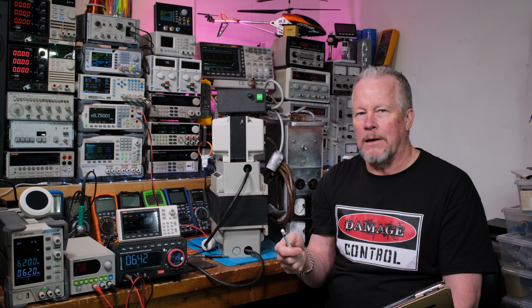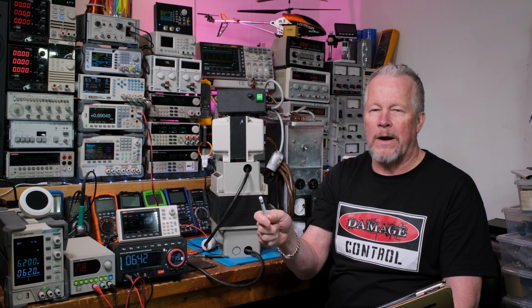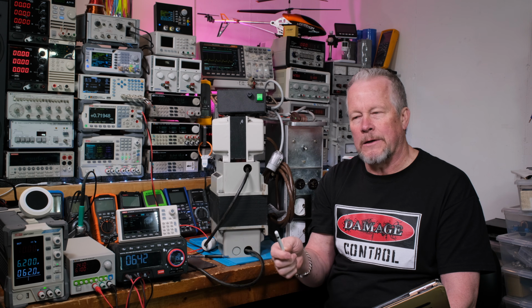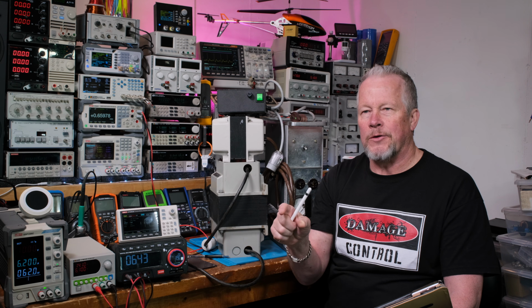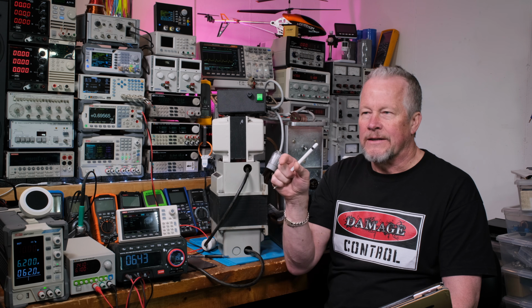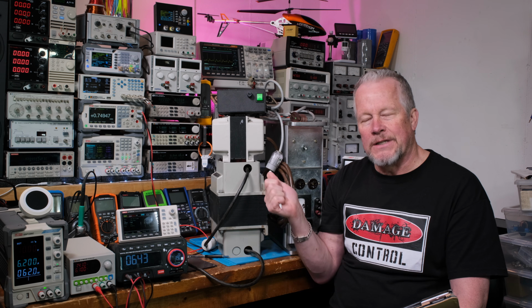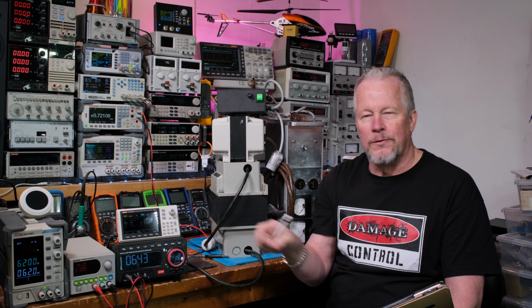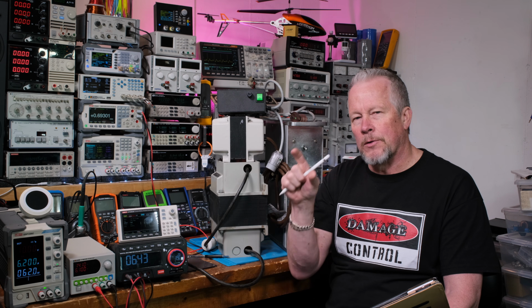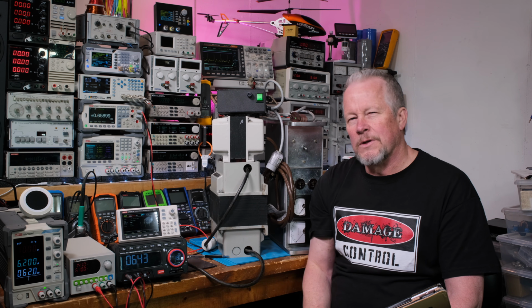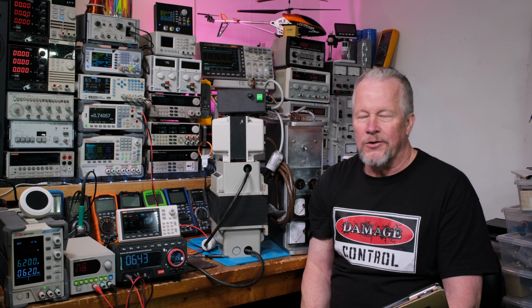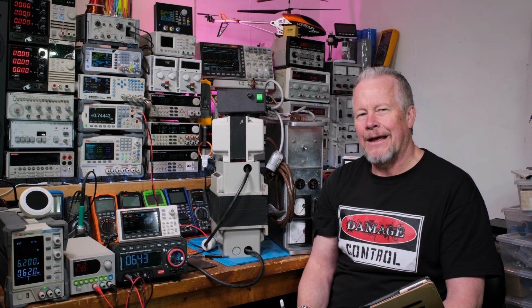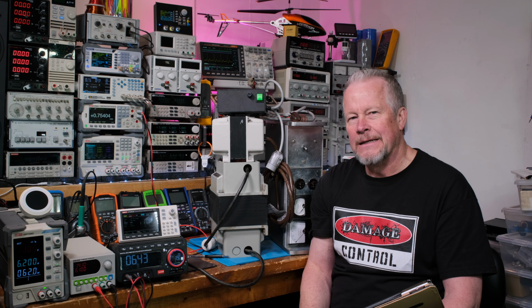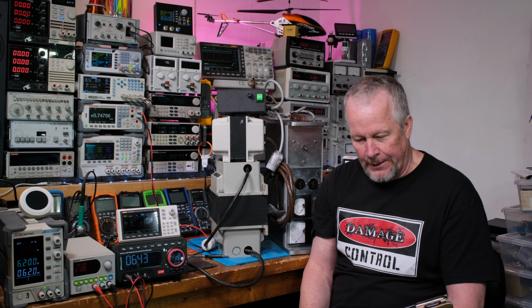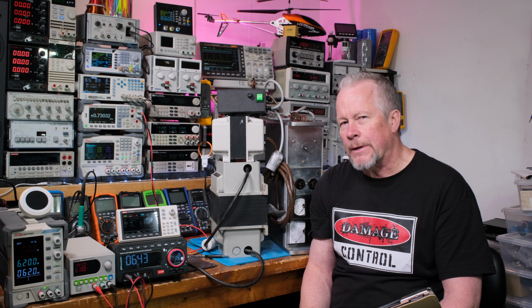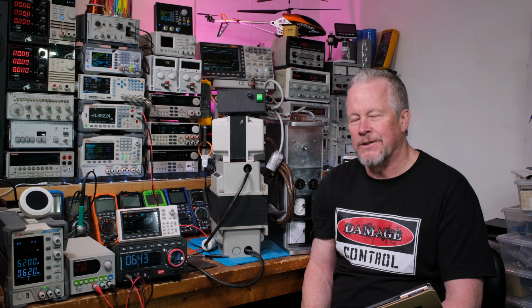Without that third pin, the ground pin, it's not keyed. Now newer 2-prong devices, since line, neutral, and ground have been developed with 3-prong devices, one of the 2-prong blades is wide to force you to put it into the neutral side. So if there was a reason it had to be polarized, we'd know which side was line and which was neutral. But I don't know if you can ever count on that 100%. So you got to be safe and careful about that. Even 3-prong devices, people can wire them backwards, so you got to be safe about that too.